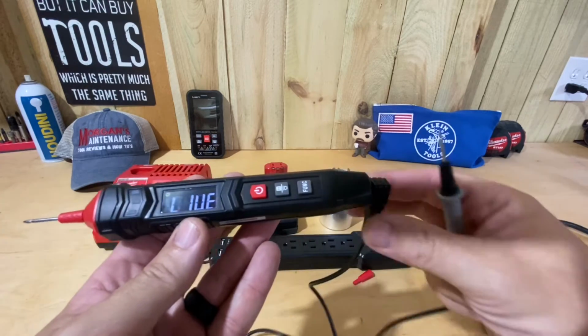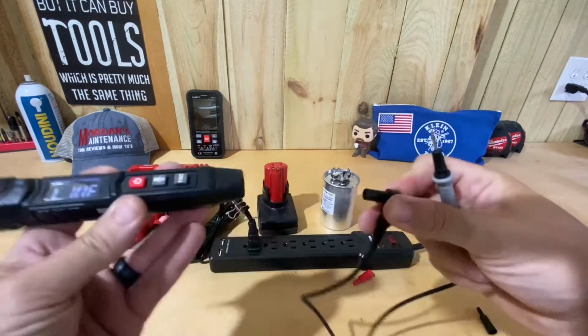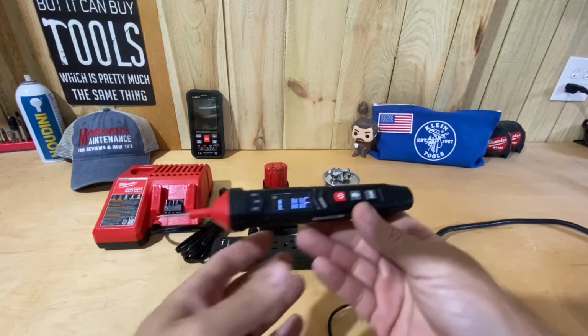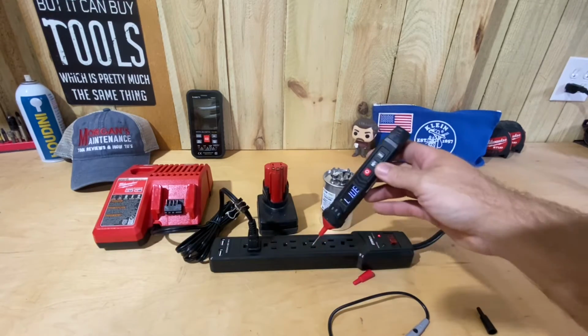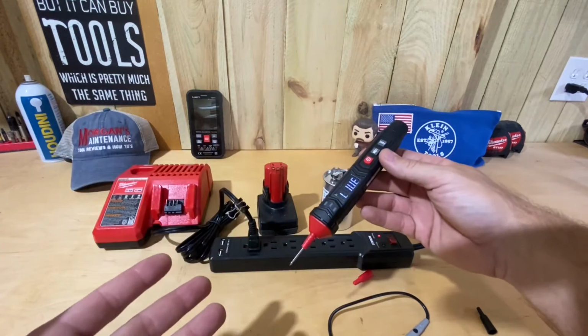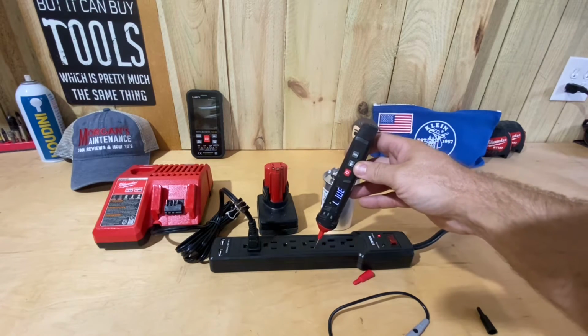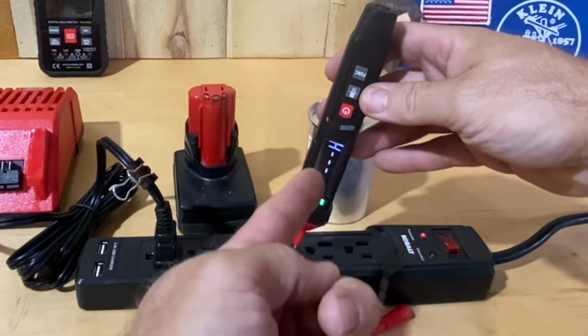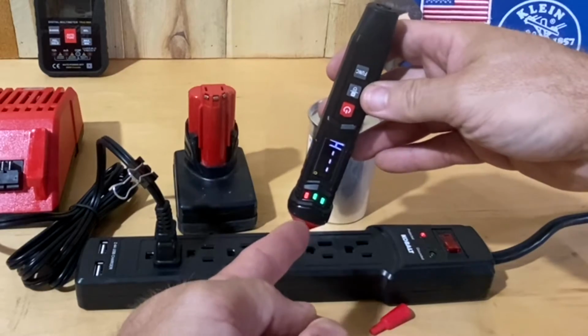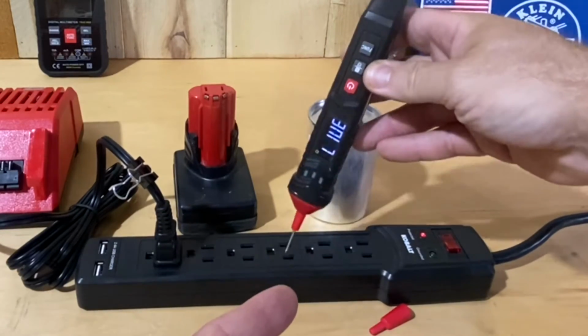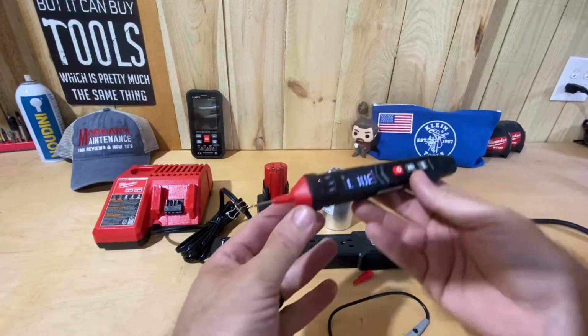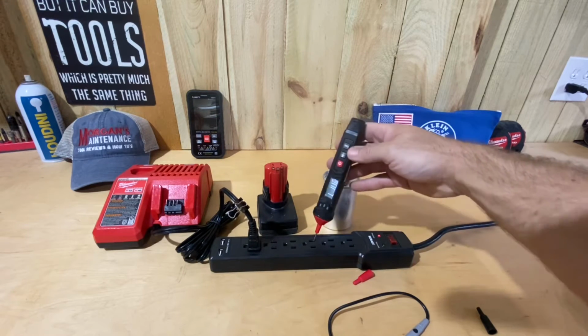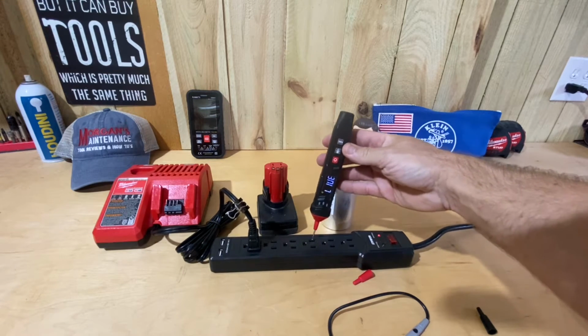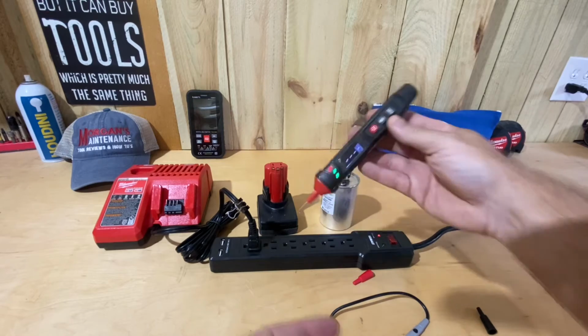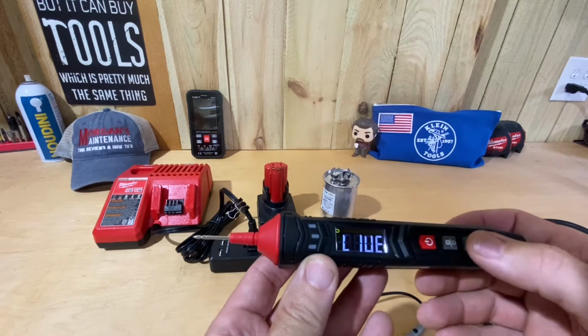Even though it's not a non-contact voltage tester, it saves me from having to actually have test leads out. I can put the probe in the hot side of this plug here and I get high voltage and audible beeps every time. When I stick it somewhere that's not live, on the neutral side, I get nothing. So that's a neat feature to have as well.